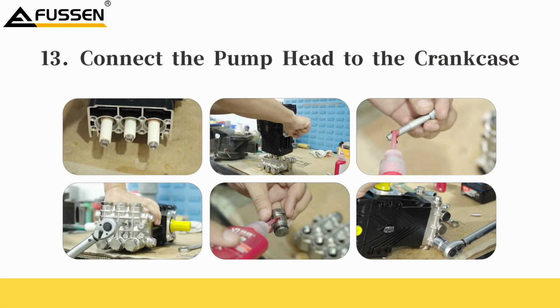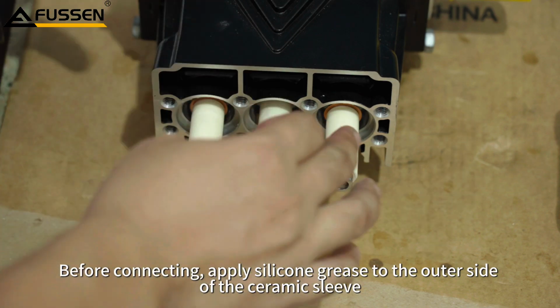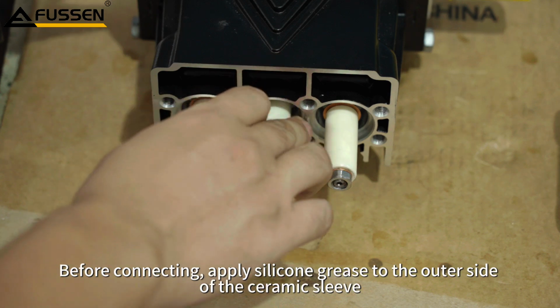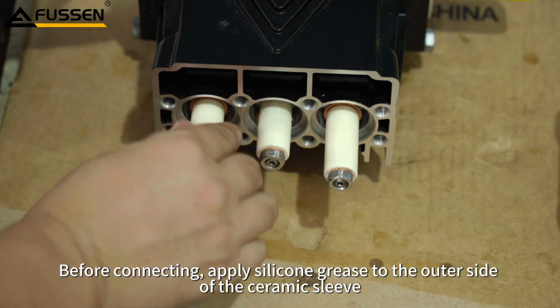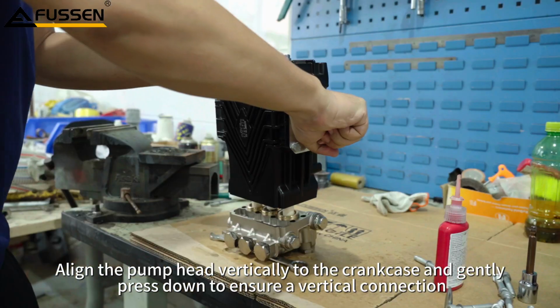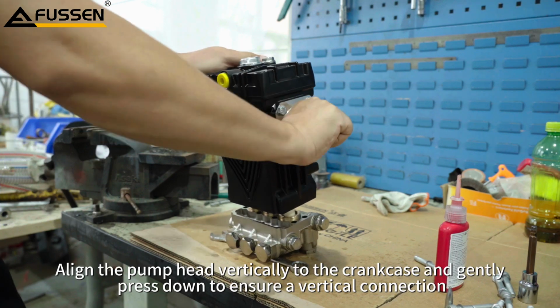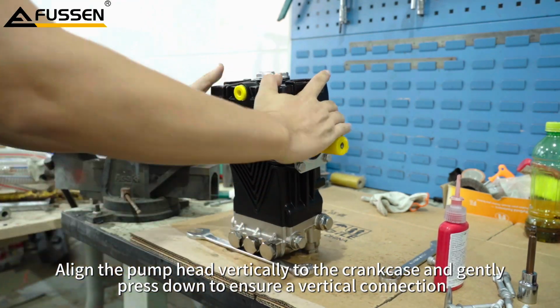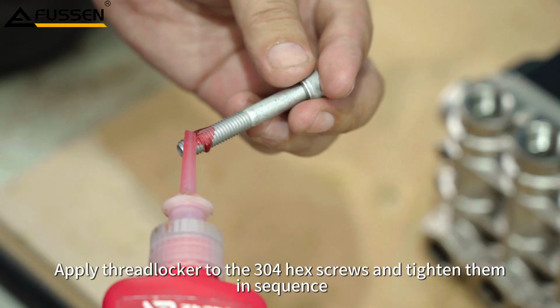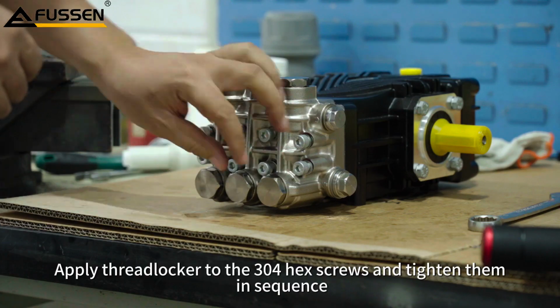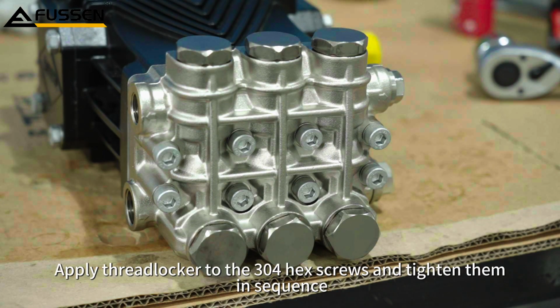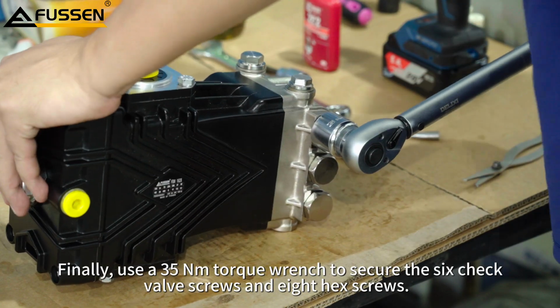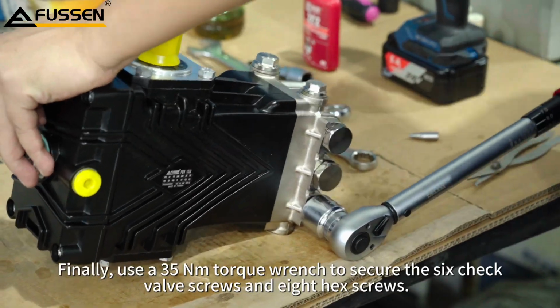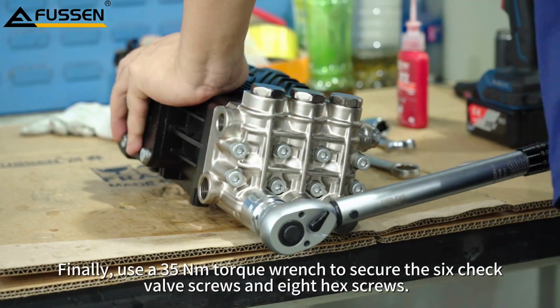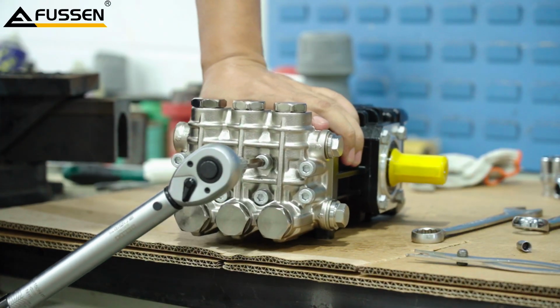Connect the pump head to the crankcase. Before connecting, apply silicone grease to the outer side of the ceramic sleeve. Align the pump head vertically to the crankcase and gently press down to ensure a vertical connection. Apply thread locker to the 8 hex screws and tighten them in sequence. Finally, use a 35 Nm torque wrench to secure the 6 check valve screws and 8 hex screws.